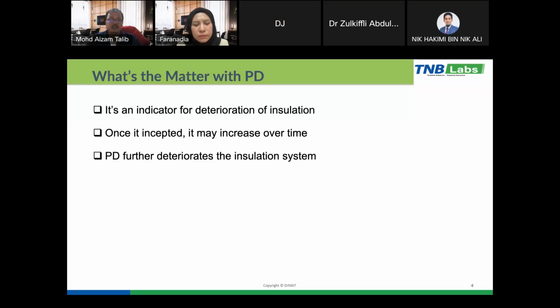Why? Because the difference is the insulation used to install these primary equipment. For the AIS, we use air, but for high population density areas, normally the insulation used to build this substation is gas. That's why sometimes we call this substation a gas insulated substation.